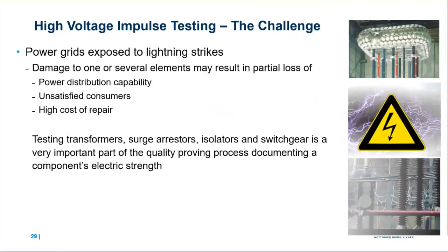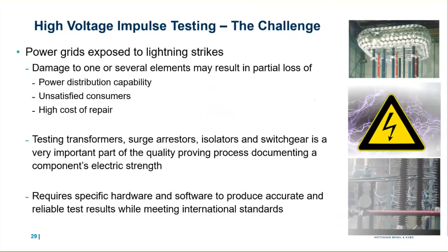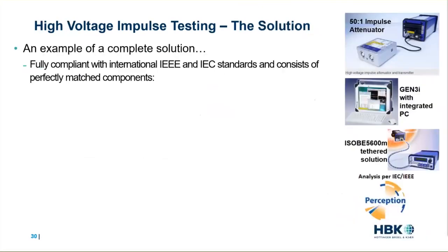Here you're testing transformers, surge arresters, isolators, and switchgear, which is very important in order to prove the quality, and you need to actually prove it by documenting the component's electric strength. Now, this requires specific hardware and software to produce accurate and reliable test results while you're meeting the international standards.